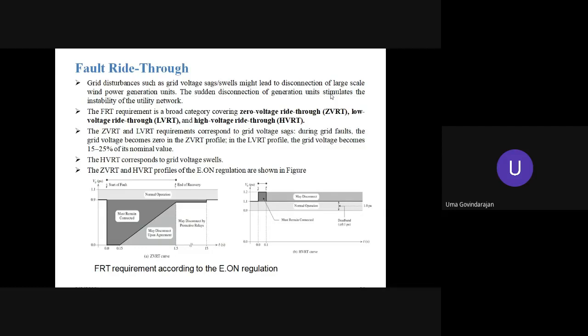Zero voltage: how long can the induction generator remain connected even if the grid voltage is 0? Second, low voltage ride-through: how long will the induction generator, the wind electric generator, stay connected to the grid? It is about the duration. For what duration will the generator stay connected to the grid, with the grid voltage at 0, or less than the rated voltage, or higher than the rated voltage?